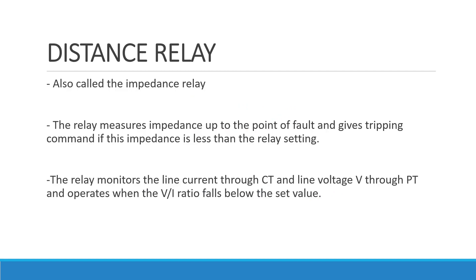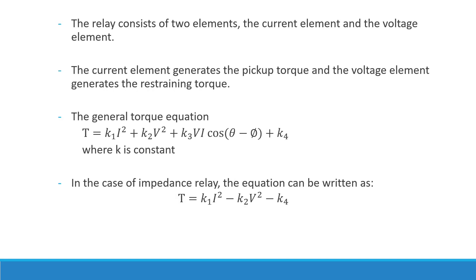Distance relays are also called impedance relays. The relay measures the impedance up to the point of fault and gives the tripping command if the impedance is less than the relay setting. This type of distance relay is mostly used for transmission overhead lines. The relay monitors the current through the CT and the voltage through the VT and operates when the V/I ratio is less than the set value.